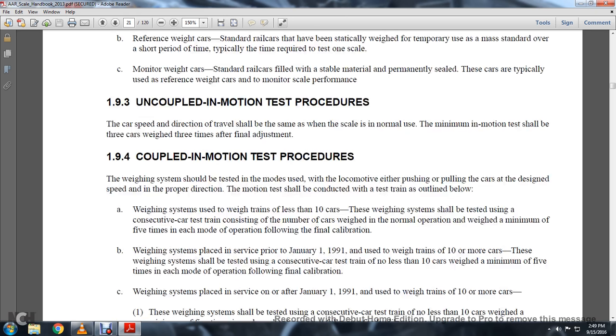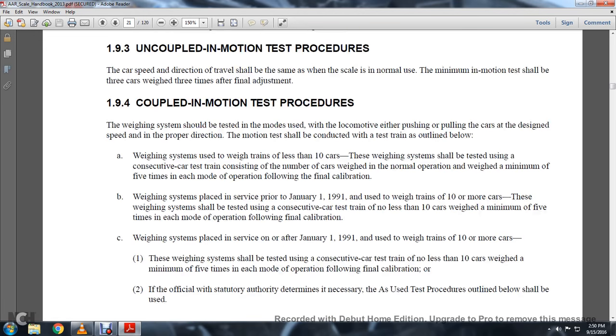1-9-4: Coupled In-Motion Test Procedures. The weighing system should be tested with modes of locomotive either pushing or pulling the cars at designated speed in the proper direction. The motion test should be conducted with the test train outlined. The weighing system used to weigh trains of less than 10 cars shall be tested using a consecutive car train consisting of the number of cars weighed in normal operation, weighed a minimum of five times each mode of operation following the final calibration.